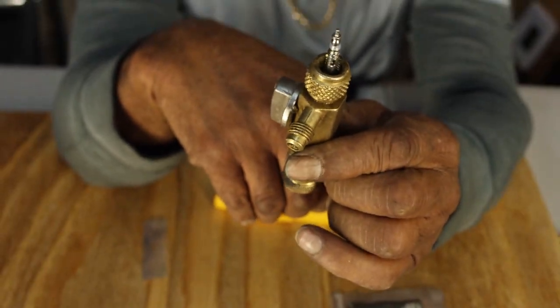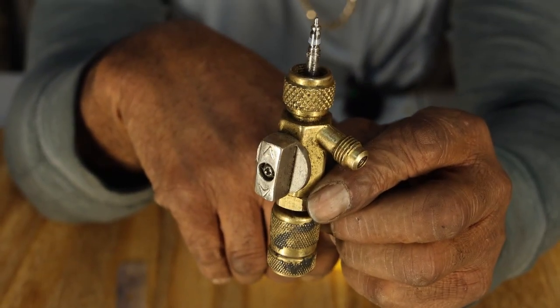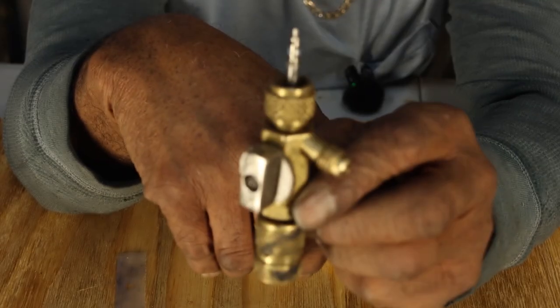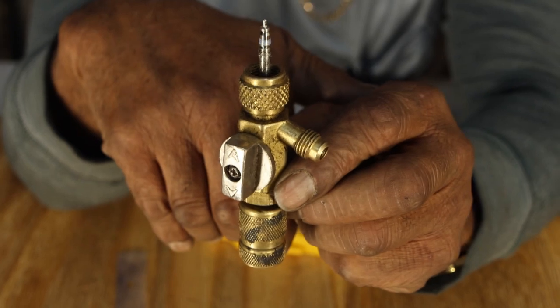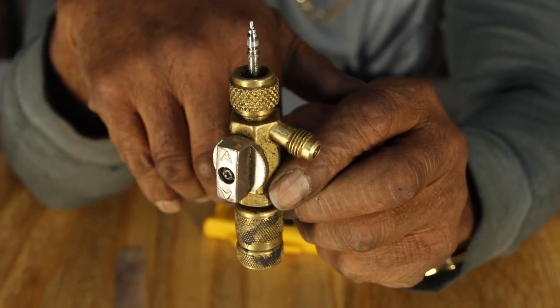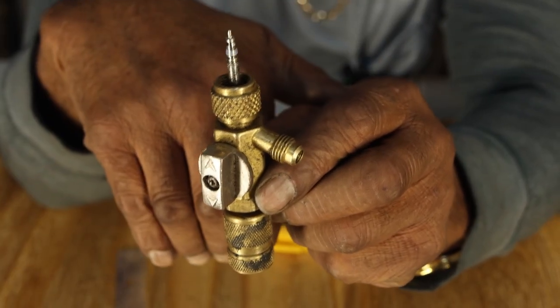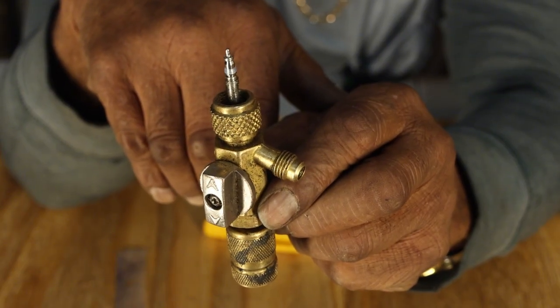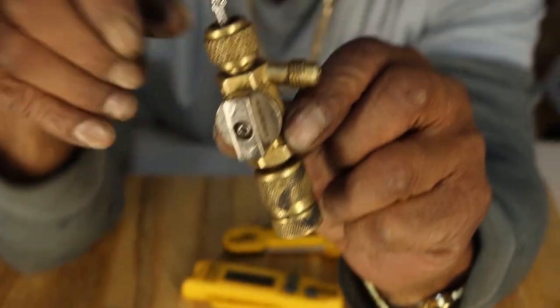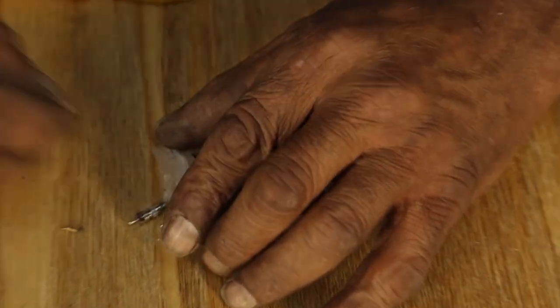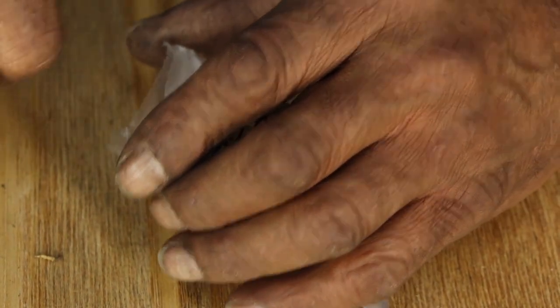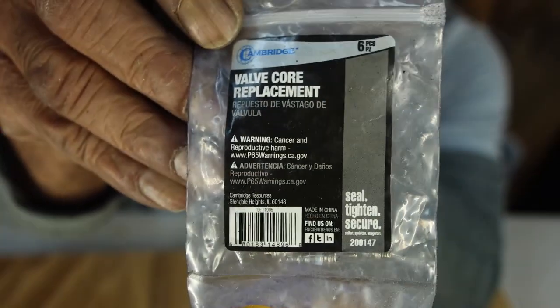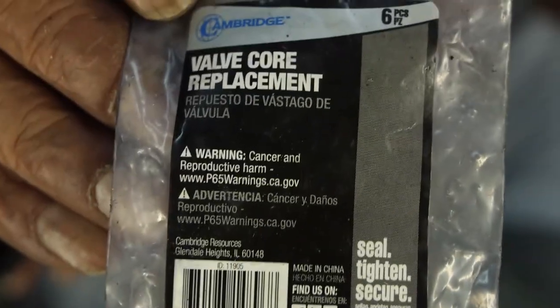It's a valuable tool. Sometimes, 80% of the time when we go to a system that's low on Freon, the Schrader valve was the problem. And the only way to remove that Schrader valve is to recover all the Freon out so you can take the Schrader valve out and not lose the Freon, or to have one of these tools. Very valuable, must have. Schrader valve core stem remover. Okay. These are replacement Schrader valves that I keep on my truck because, as I said, a lot of times the Freon is leaking from the Schrader valve.